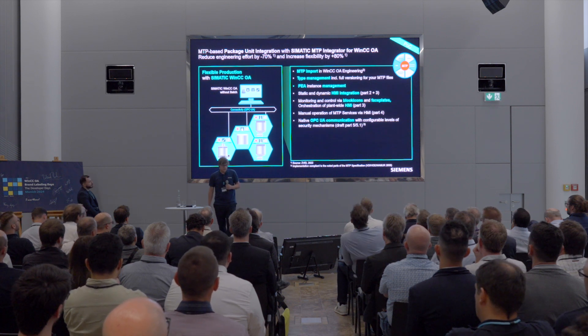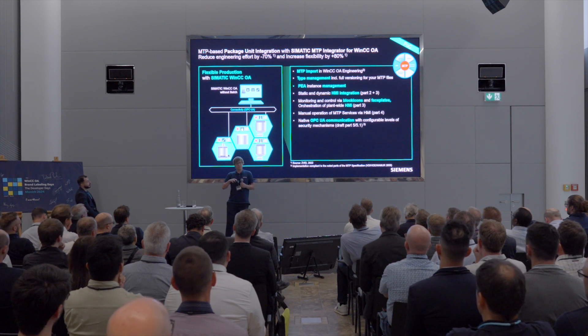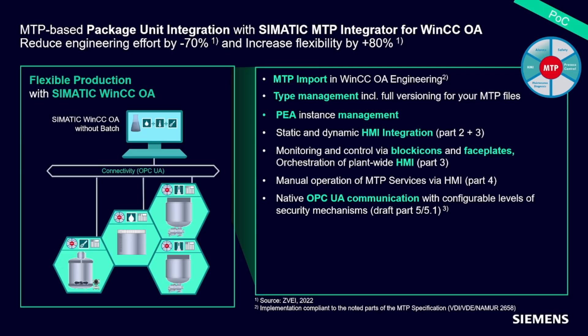What is important at the SCADA level? There is a reduction in engineering effort and increased flexibility. The SCADA system needs a feature to import and validate MTP files, then a type management system — because the MTP file is a type descriptor of a machine or unit, similar to how a USB driver describes a type of device, not a specific instance. We also need the ability to manage instances — the actual machine instances — creating machines in the SCADA system based on types. Finally, we need features to generate the full content: connections, tags, pictures, and the link to the batch system.